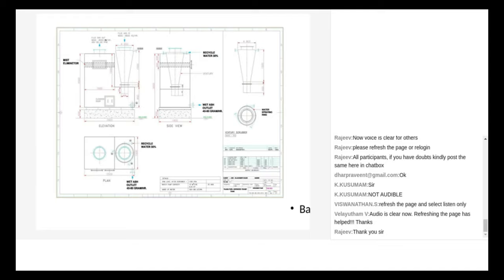You normally save around 5 to 6%. That is, if it's a 2-tonner boiler, you save about 700 kgs of fuel per day, which gives him 10 lakh savings very easily. But his problem is never about the 10 lakhs. If you talk too much about it, he says that's not my real problem. My real problem is about continuing with this boiler, keeping the chimney exhaust in control. And that is where he needs your help.